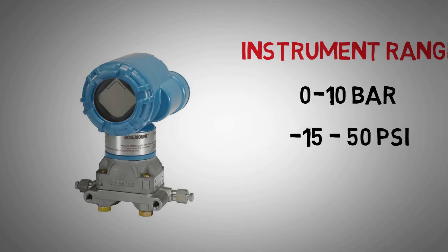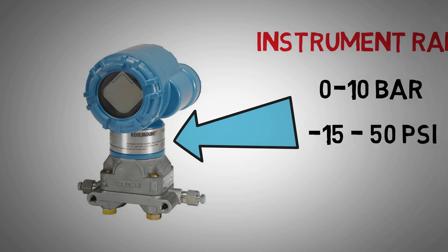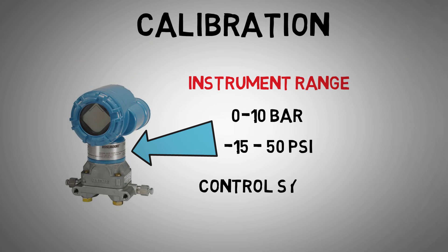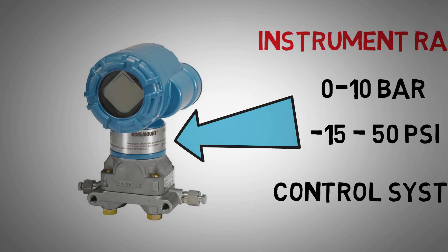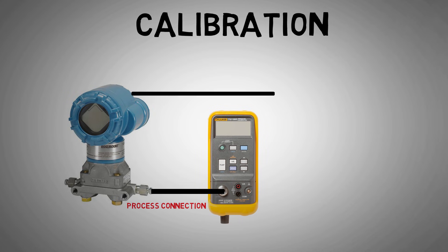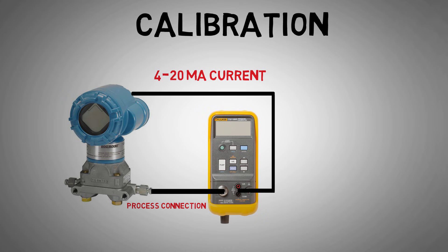We would first need to know the range of the instrument so that we know what test equipment to select and to calculate our test points. The range might be printed on data labels on the instrument, or we could look at the control system block we are connected to in order to find the range. We would then connect a calibrated, suitably ranged pressure pump or calibrator to our instrument via its process connection. We would also connect the transmitter electrically to a calibrator to test the 4-20mA current signal that the transmitter gives out to different inputs.